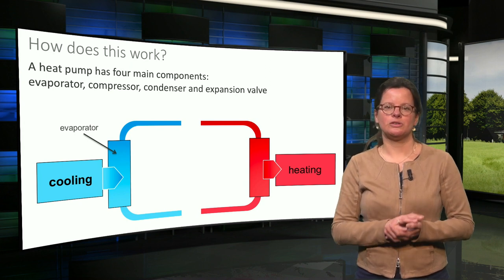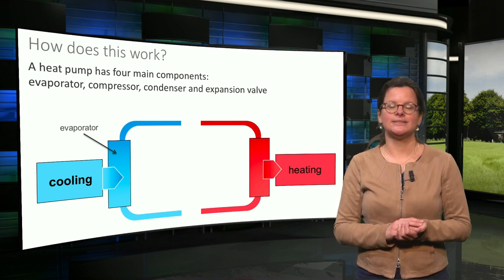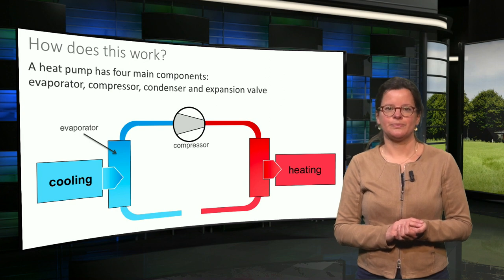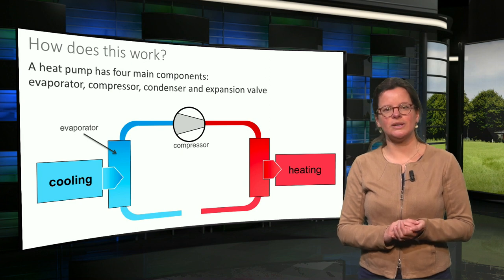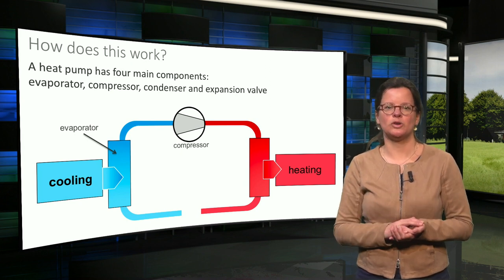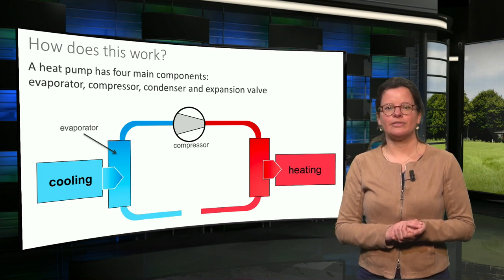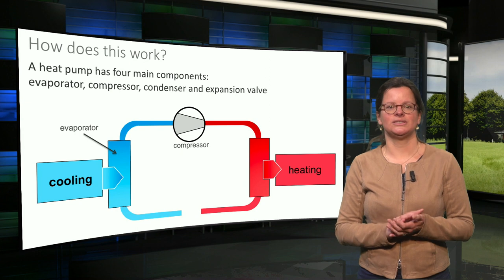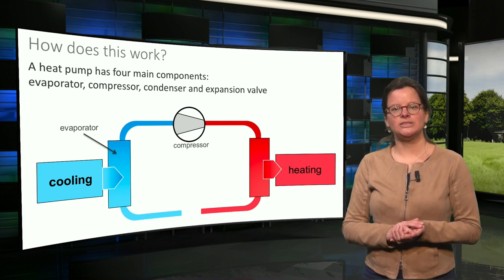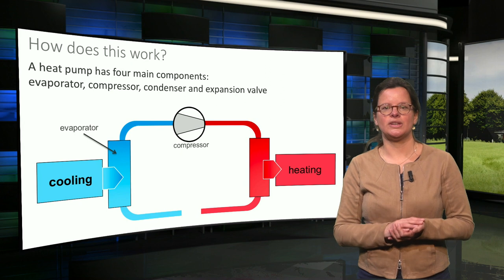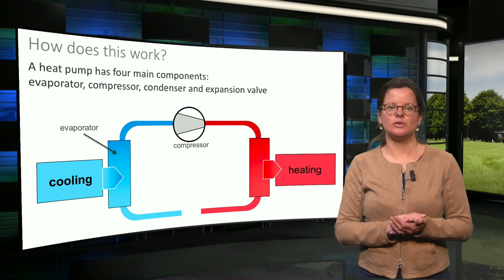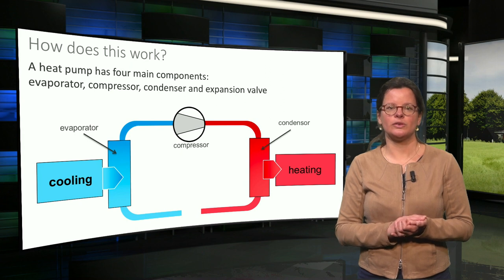In order to further increase the temperature of the refrigerant, which is now a gas, a compressor is used. By compressing the gas, its temperature is increased. The achieved temperature must be higher than the temperature of the hot body in order to be able to transfer the heat. This compression of gas requires the input of electricity. The gas with the increased temperature then passes another heat exchanger where heat is transferred to the hot body. This heat exchanger is called a condenser as the refrigerant returns to a liquid phase as a result of the heat transfer.